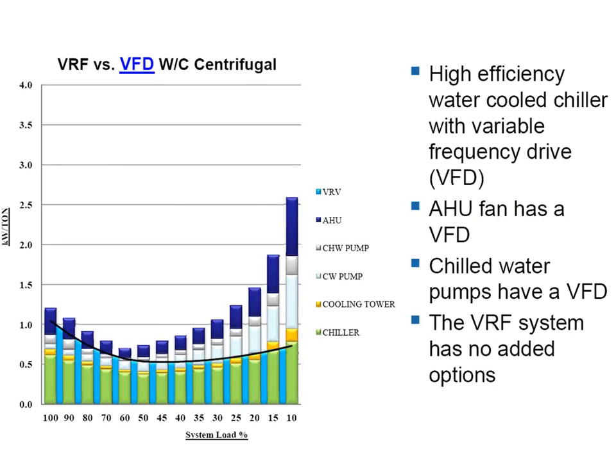Now, I would argue that it's still less energy than the dark blue bar for the AHU because I'm only moving 25-30% of the total air volume than I would have been moving with the all air system. But yeah, that's a good point, Jonathan. And there's probably two reasons it doesn't have that. One, this chart was made by a VRF manufacturer, right? And two, many VRF systems are not being installed in buildings that have DOAS systems.